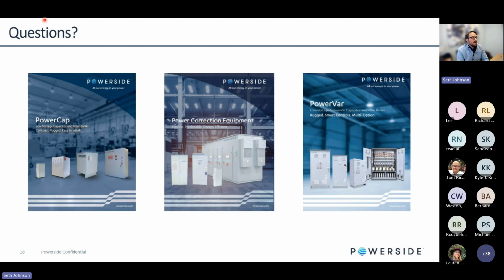Increasing voltage is always a concern when you're increasing fault current, essentially by adding solar along with utility power connection. So there are ways to mitigate that. I would say we do that in the medium voltage space, not so much in low voltage. So we'll do that with switched reactors or something similar to static VAR compensation to help bring down voltage. We've done this also in solar and wind farms where you've got very long underground cable runs for medium voltage. There's a lot of capacitance in those cables that also increases voltage. But yeah, we have run into that. We've seen that. We do have some solutions depending on the application.